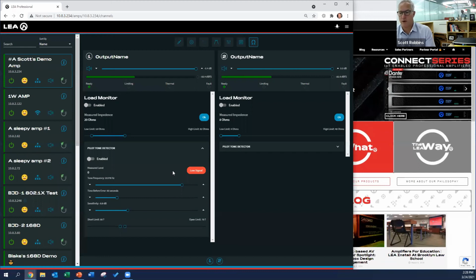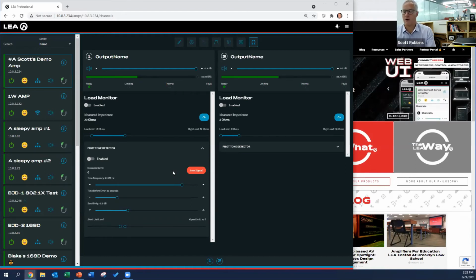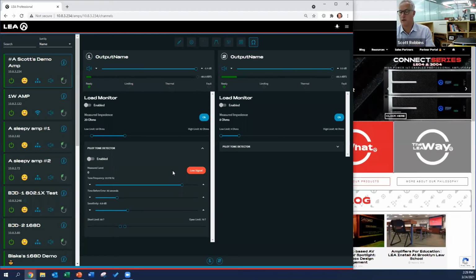This is often required in a life safety application, where you have to validate that if there's an emergency evacuation message, the amplifier can confirm all the speakers are in good working order and everything's connected. The load monitor can tell you if there's ever a problem. If a zone gets cut or a speaker blows up, it'll register that as a load event, and you can go investigate where the problem is.